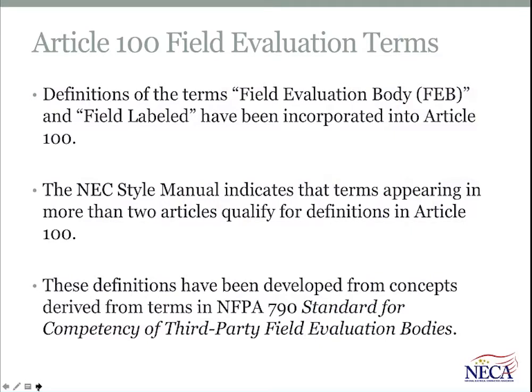There's two new definitions, and these are important to not only inspectors, but they're also important to contractors, owners, and so forth. They're definitions of the terms field evaluation body and field labeled. And they have a direct relationship to the standard from which they're derived, which is NFPA 790. That's the standard for competency of third-party field evaluation bodies. Oftentimes, inspectors require third-party listing or product certification as a basis for approvals. And if equipment comes in and doesn't bear that indication, or if there's evidence that it has not been certified or listed by a qualified electrical testing laboratory, oftentimes an inspector will provide a field follow-up report, and it often results in a field evaluation and associated report.